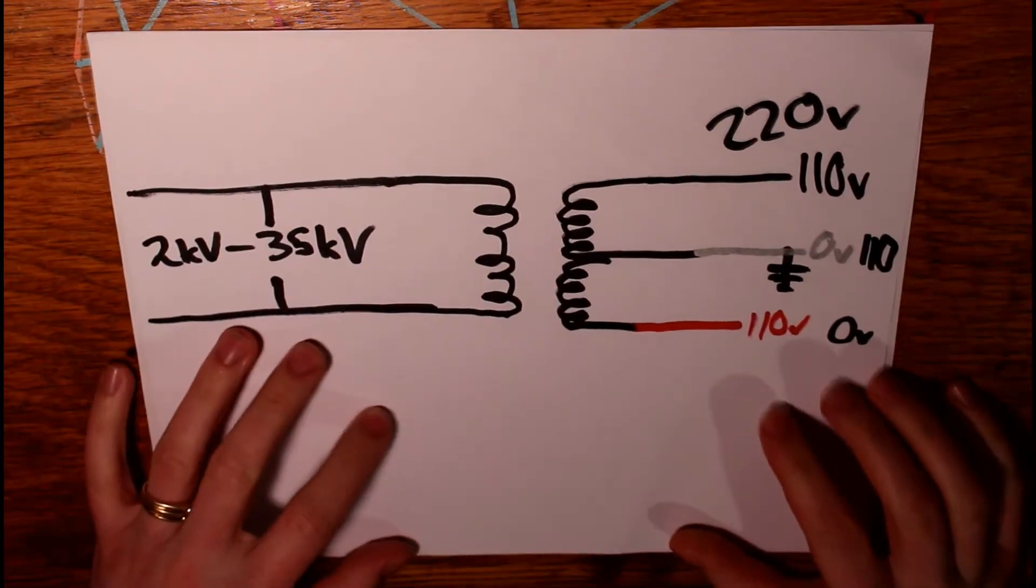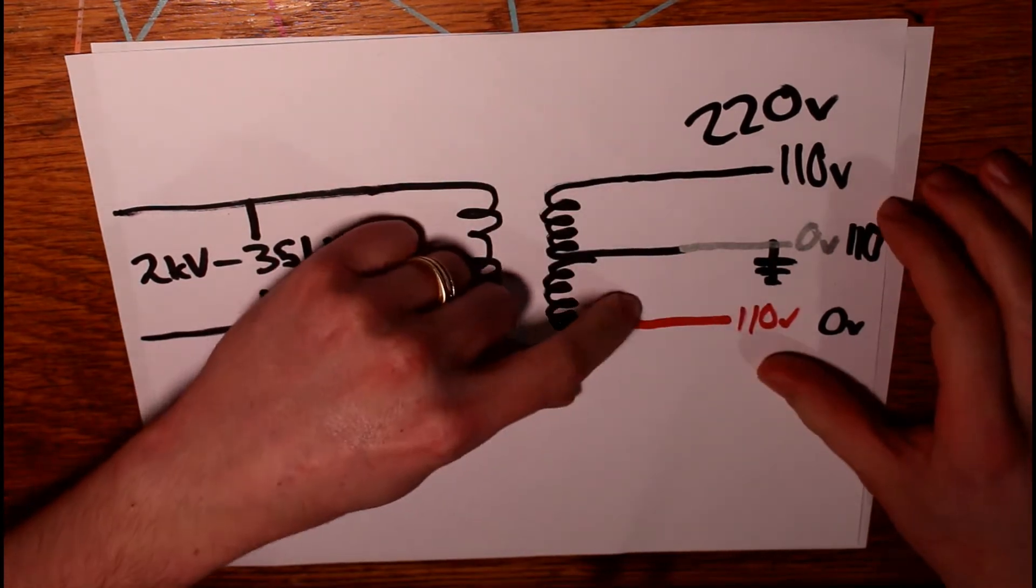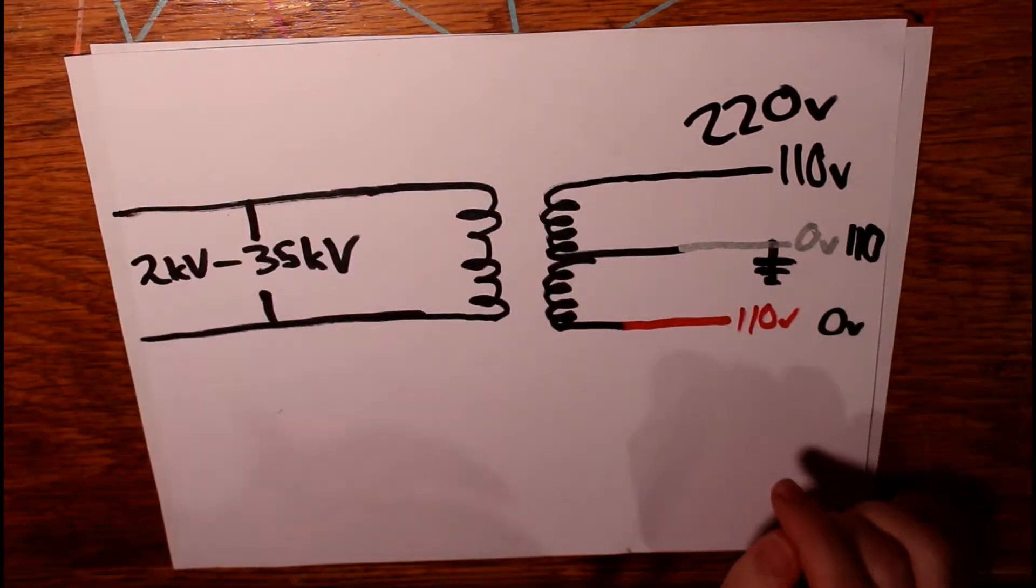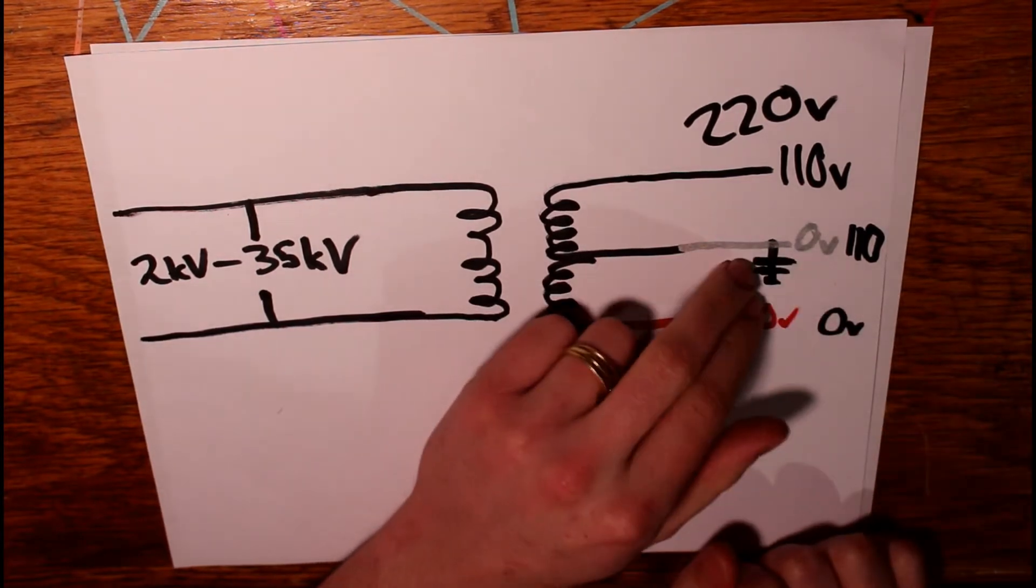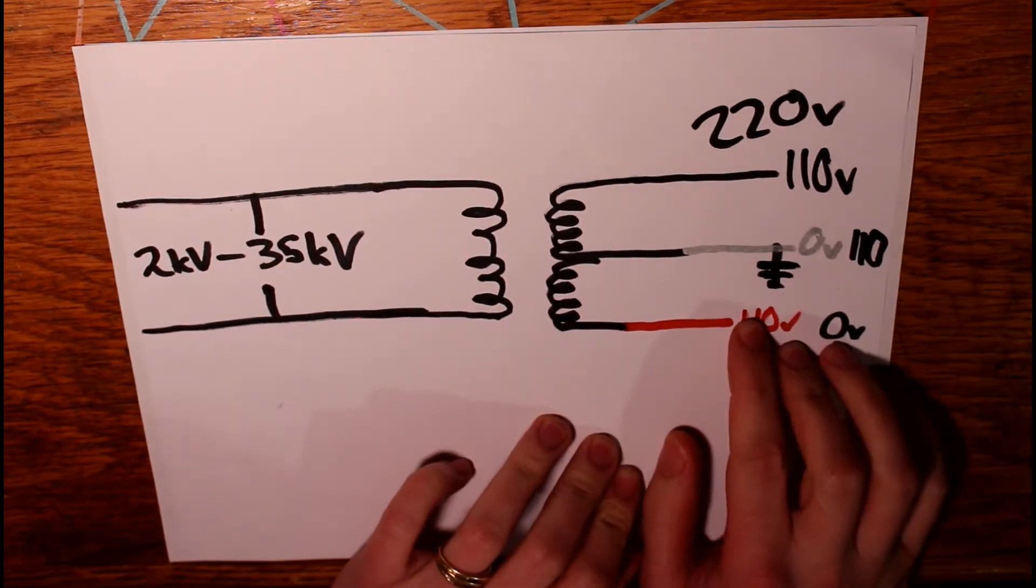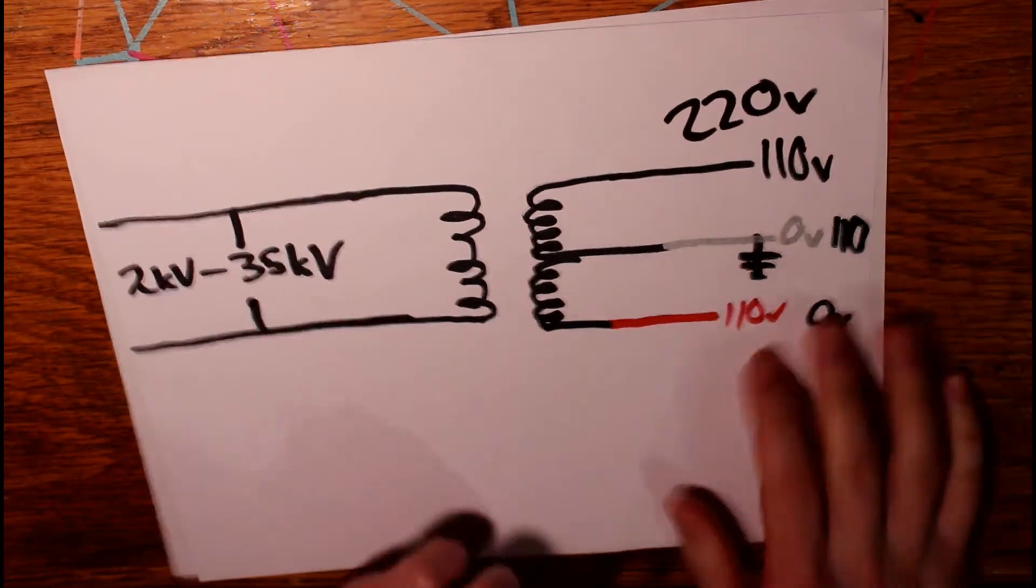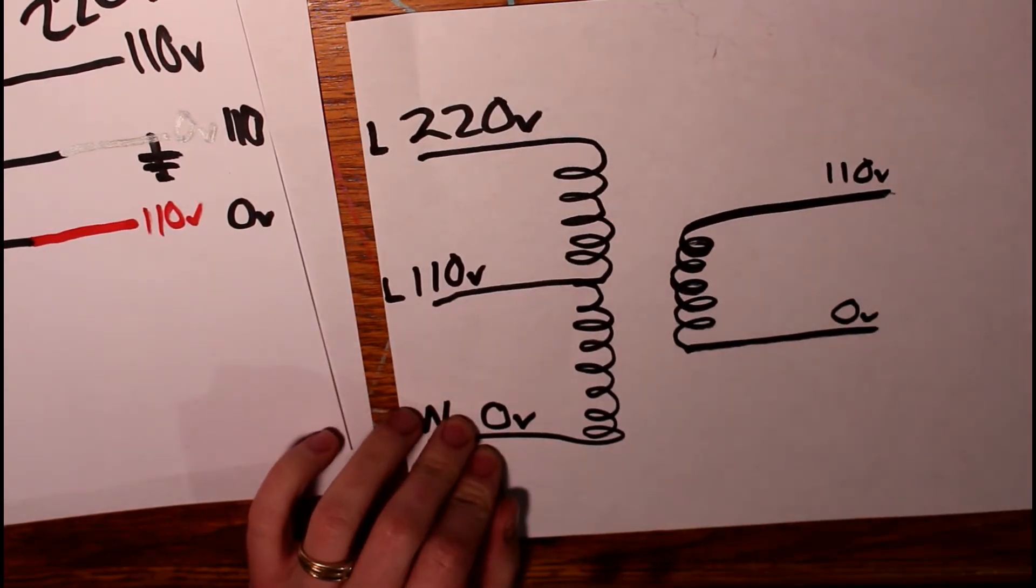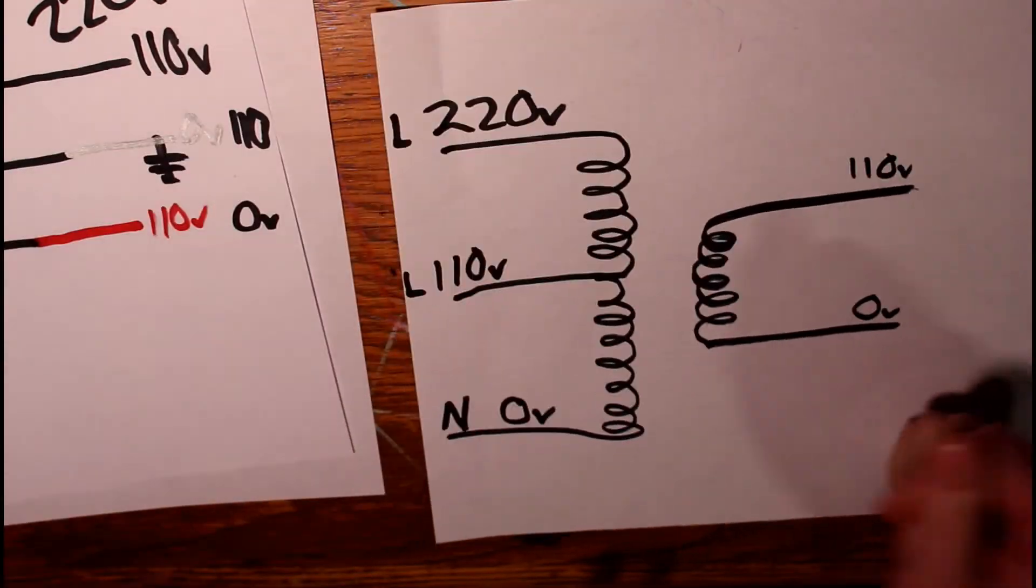For example, we saw with the distribution transformer that power comes into your house. You've got 110, neutral, zero, and another 110. But until you've actually got a device connected up that has an earth reference, a ground connection, then there's no reason why you couldn't just as easily call this zero volts, 110 volts, and 220 volts. And so then you look at something like this transformer, where now neutral is your bottom leg of your transformer, your zero volts. And your line voltages are up here, 110 and 220.